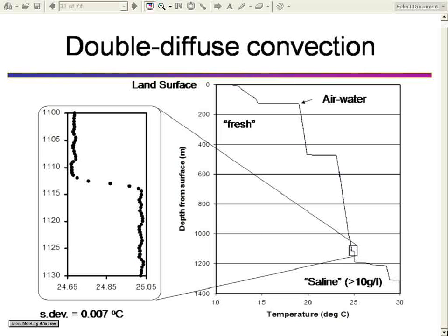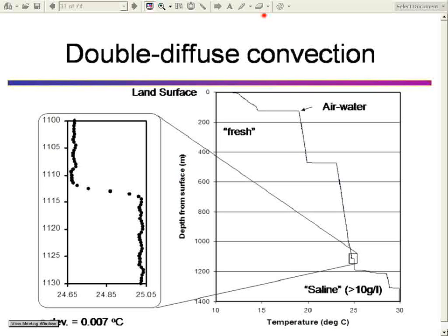Looking at this little step here, we're going from 25.05 degrees to 24.65, about a four-tenths of a degree change. The variance, the standard deviation is on the order of 7,000ths of a degree. In terms of spatial resolution, we're reporting the temperature every half meter. Over one meter, we see the bulk of the temperature change. The spatial resolution is on the order of 1.2 to 1.3 meters.